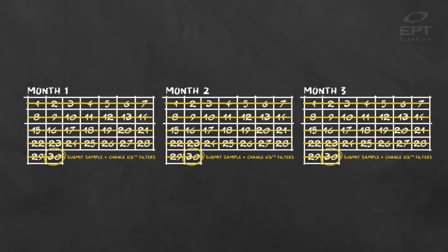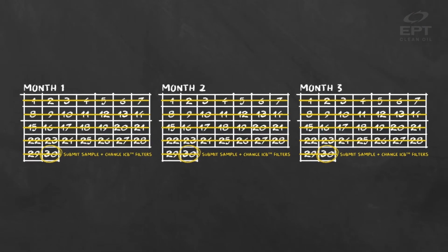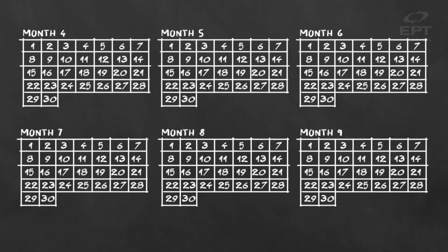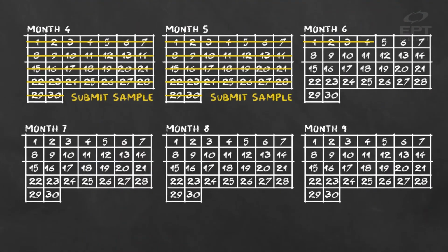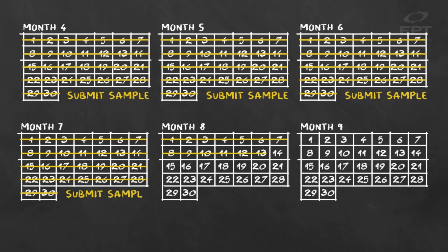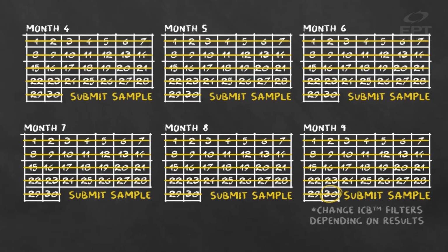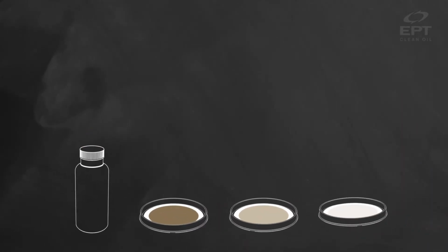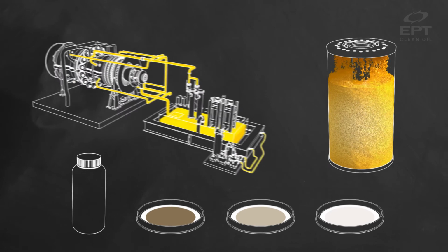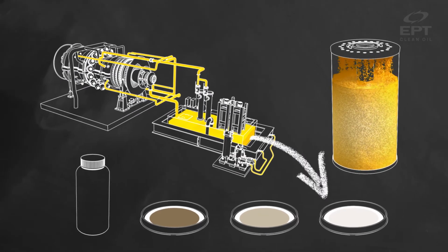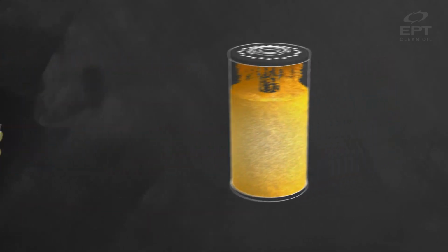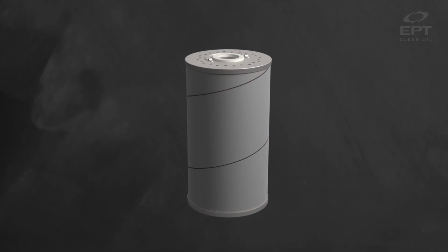After 3 months, in review of the documented trend line, filter change intervals will decline. Fluids back in specification go into maintenance mode, with filter change requirements shifting to every 6 or 12 months, depending on results. Continued sampling and proactive maintenance strategies will ensure shifts in fluid quality can be easily addressed and new filters can be installed in a timely manner.